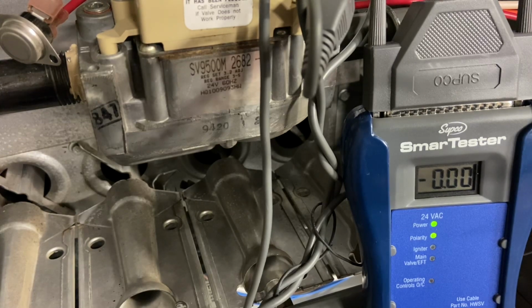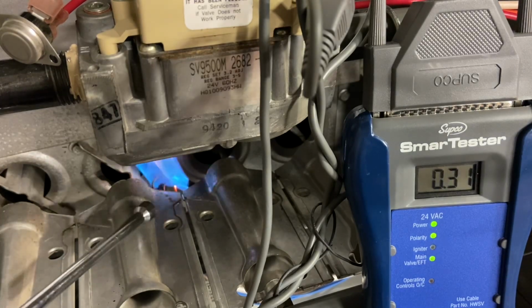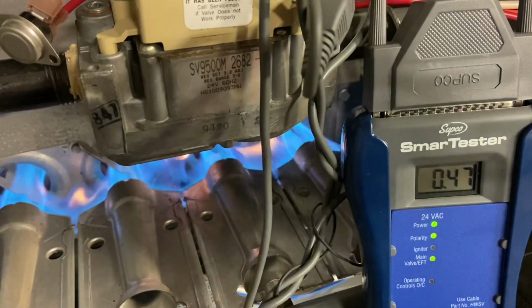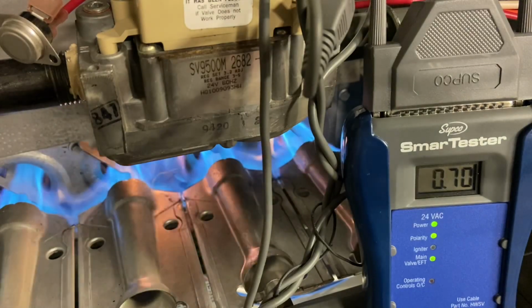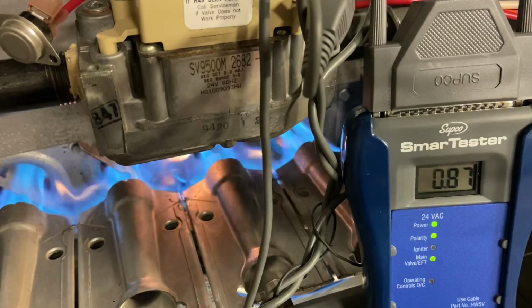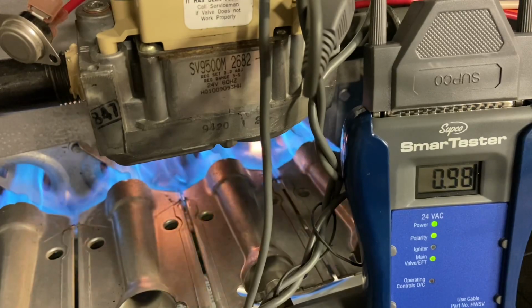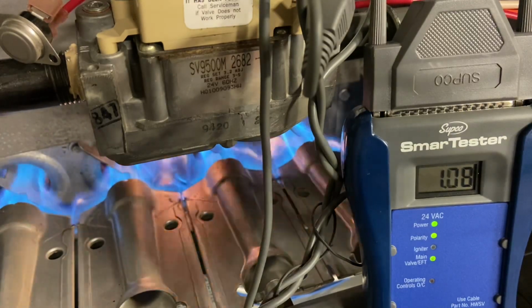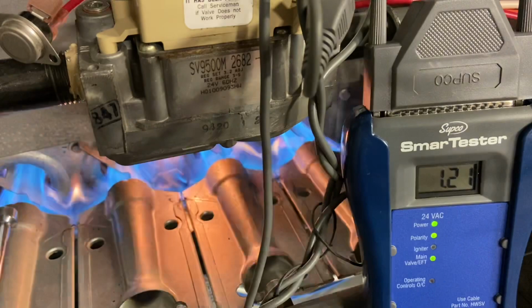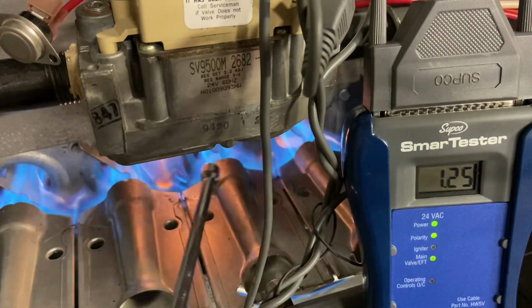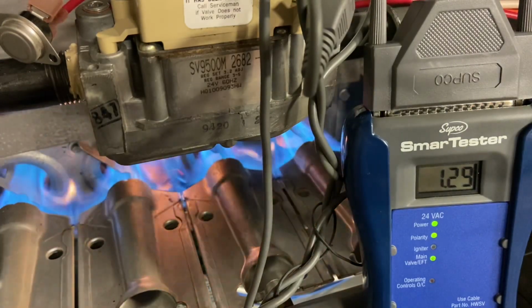Our inducer fan energizes, pulls it back into our pressure switch. We hear a little bit of gas. We see the pilot light burning right there. Now we ignite the main burners all the way across. Now the color of these flames is improper because it's burning on the wrong gas, the wrong pressure, and the wrong orifices. But you can still see that the flames are burning inside of the heat exchanger, and you can see how the crossover tube ignites.